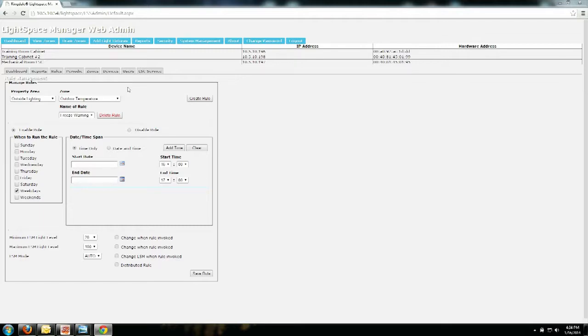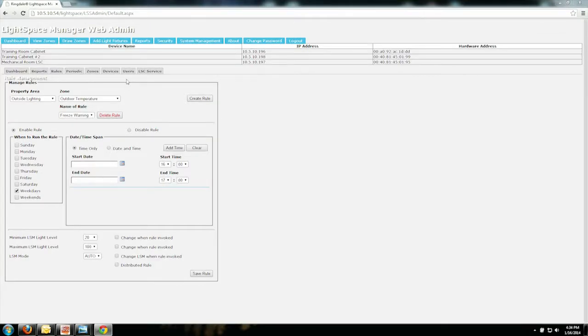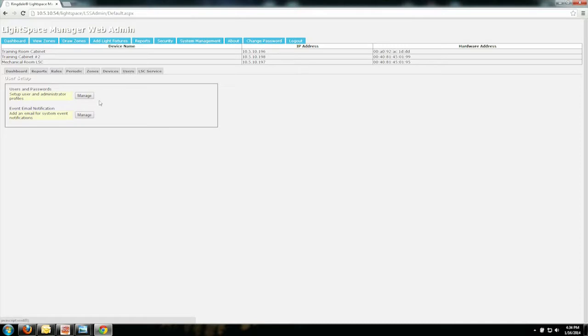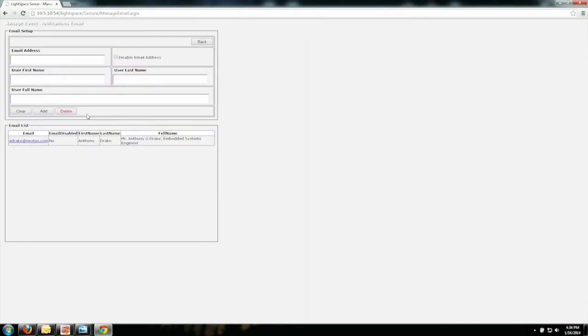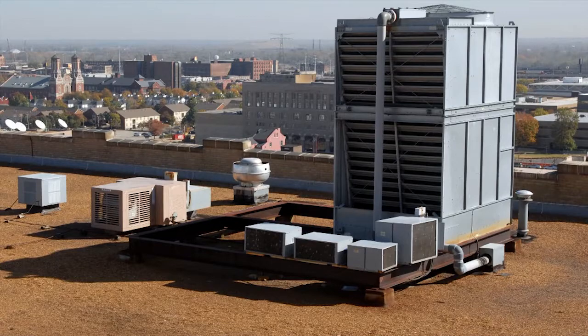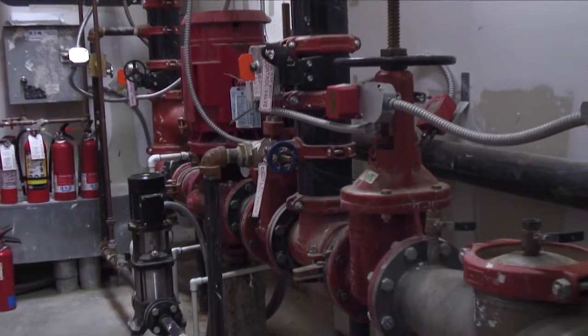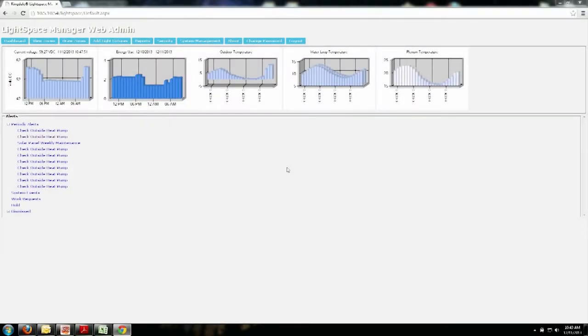Active BMS has the most powerful rule engine of its kind. Simple rules can be applied to lighting zones, air conditioning zones, or any other electromechanical device. Also, complex rules can be applied taking multiple sensor inputs and applying algorithms to trigger actions like sending an email or turning fans, air handlers, or pump equipment on or off, or adjusting a valve with a 0 to 10 volt input.